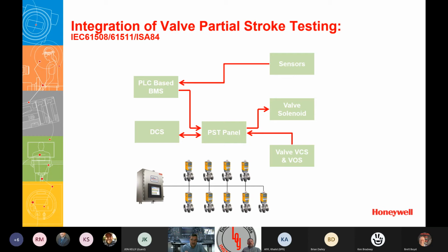So we energize, re-energize, and we go 10, 11, 12, 13, 14, 15 milliseconds. Eventually, as we drop the pressure in the cylinder and have an interval, we get a slight recovery. So we get to move the actual wetted parts, the disc in the seat. With every subsequent pulse, it may be on the 4th one that we travel the disc enough that the valve open switch changes state.